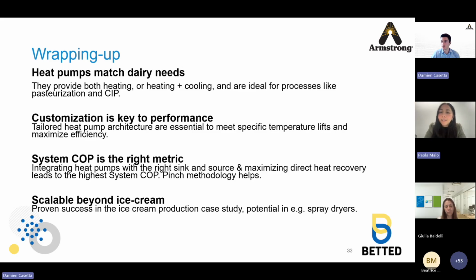Yes, sure. So Saravanan asks, what is the typical payback period while shifting to heat pump with combined heating and cooling from the individual conventional system for both heating and cooling? Yeah, that really depends on the electricity prices, the gas prices, and the project. So I would say there is no universal answer to this. It depends on the subsidies, if there are any. Now we see very good news in that regard at the European level, but it can range anywhere between a few years and, I would say, two digits. So then you make the project happen or not. It's down to the details, definitely.